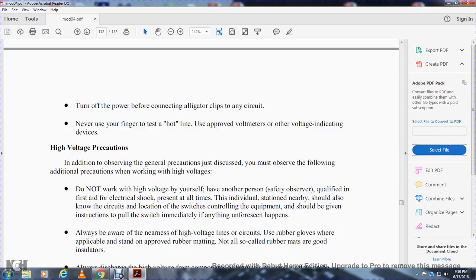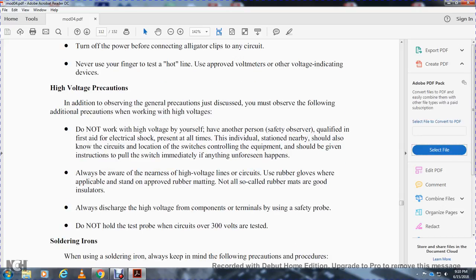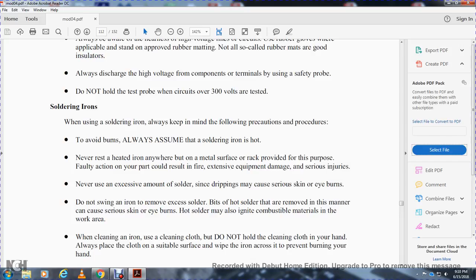High voltage precautions: in addition to the general precautions, observe the following when working with high voltage. Do not work with high voltage by yourself — have another person present as a safety observer, qualified in first aid for electrical shock, at all times. The individual stationed nearby should know the circuit and the locations of controls for the equipment and should be ready to pull the switch immediately if anything unforeseen happens. Always be aware of the nearest high voltage lines and circuits. Use rubber gloves where applicable and stand on approved rubber mats. Always discharge high voltage from components and terminals using a safety probe. Do not use test probes when circuits over 300 volts are being tested.